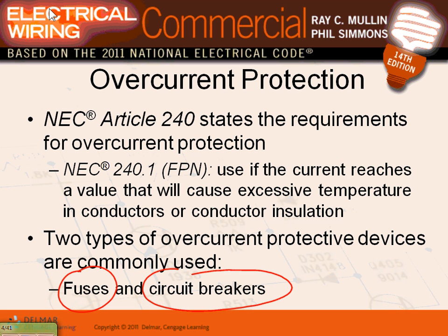Will cause excess temperature to the conductors. This is just sizing for the most part. Generally speaking, everything needs to be protected from overcurrent, right? If I have a conductor like this, here's my conductor right in here, I need to put an overcurrent protection device, 20 amp, on this number 12 conductor so it doesn't allow this baby to heat up in a short circuit condition and create a fire. So this guy will handle it.